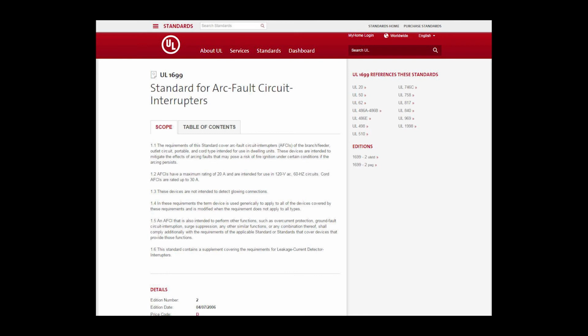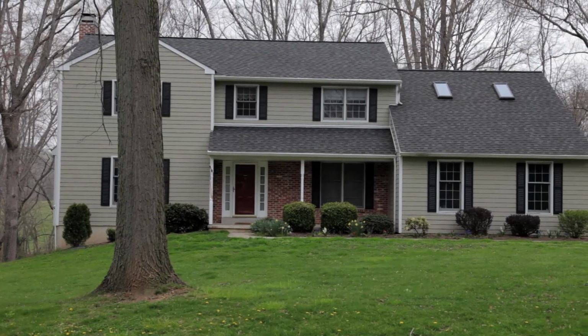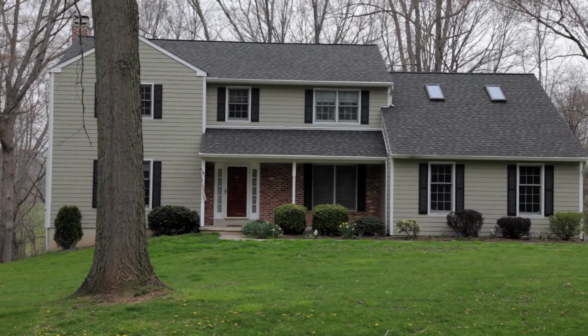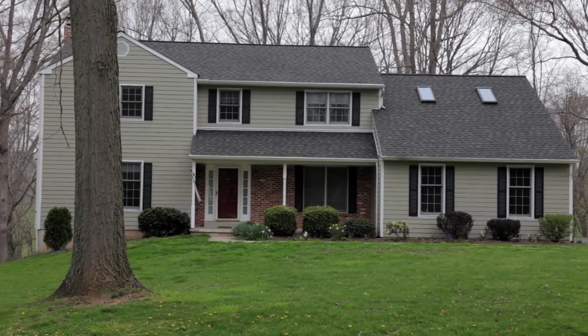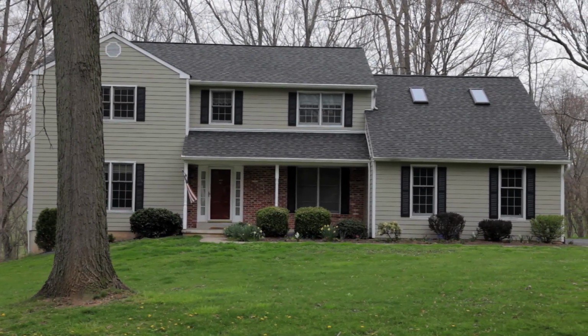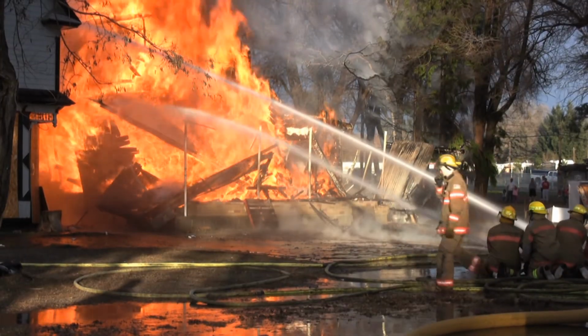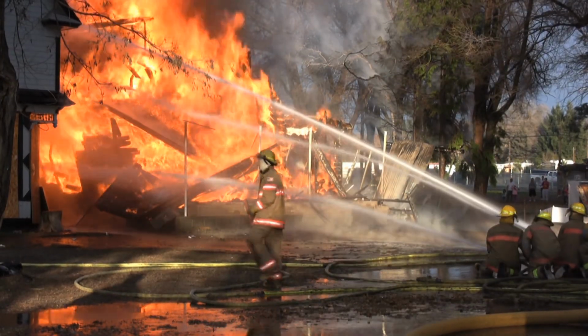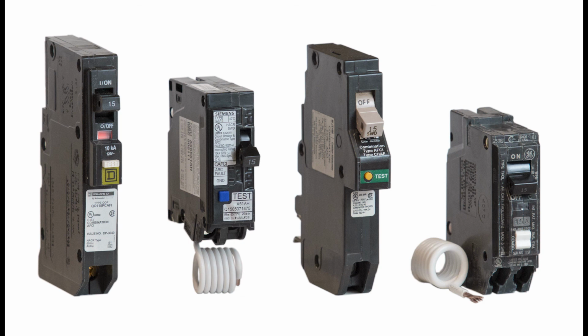All arc fault protection devices should comply with UL 1699 requirements, as they are there for the homeowner's safety. Our ability to repeatedly cause a fire in real-world conditions demonstrates that the claim that standard circuit breakers can provide arc fault protection is false. Arc fault circuit breakers do work to protect the home from fires. Fire safety should not be compromised.